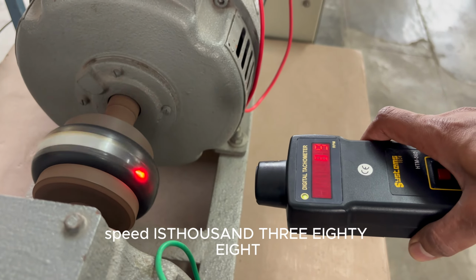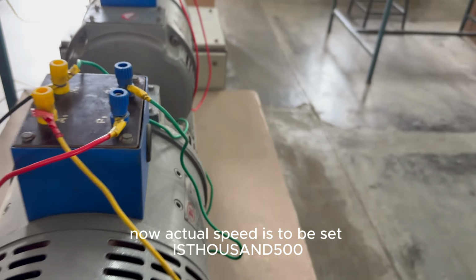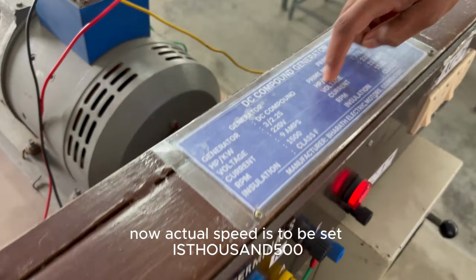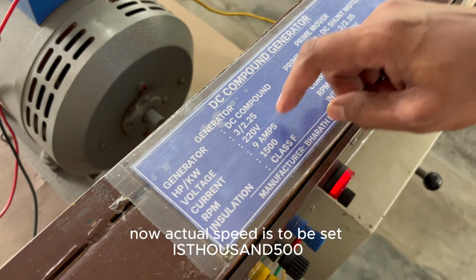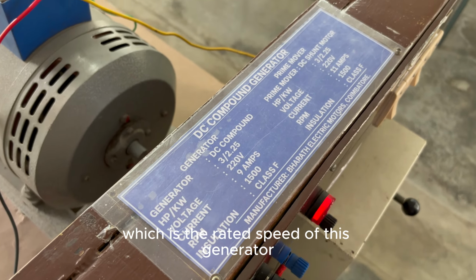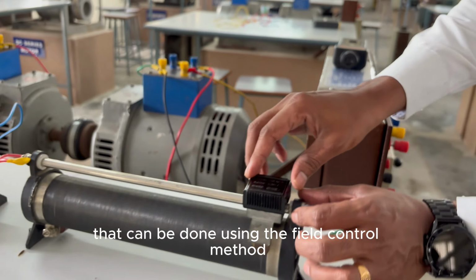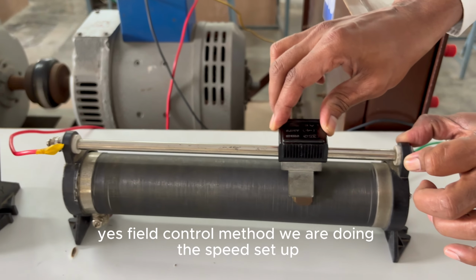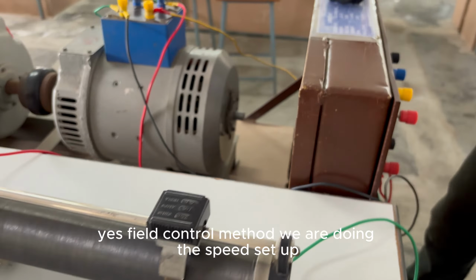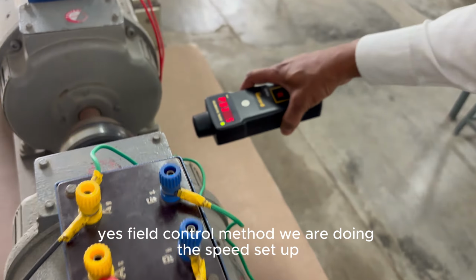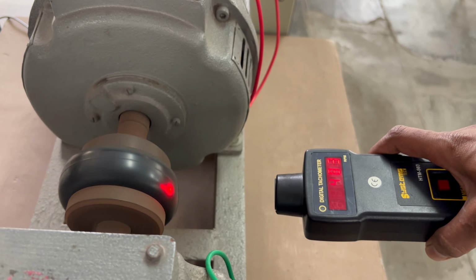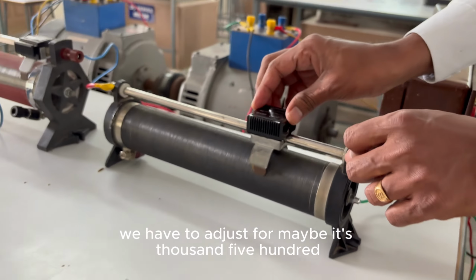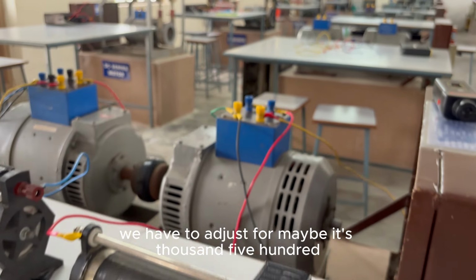Speed is 1388 now. The speed to be set is 1500, which is the rated speed of this generator or prime mover. That can be done using the field control method. I'm doing the speed setup. It is 1483, so slightly adjust. Maybe it is 1500 now.